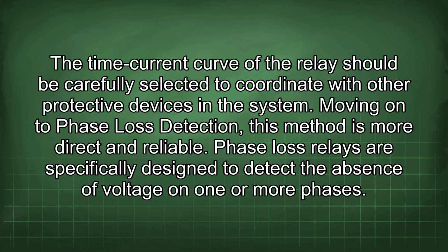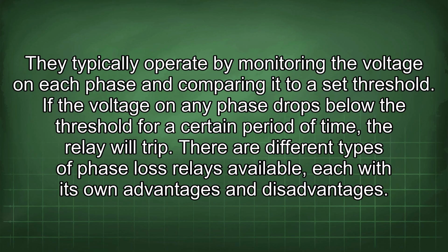Moving on to phase loss detection, this method is more direct and reliable. Phase loss relays are specifically designed to detect the absence of voltage on one or more phases. They typically operate by monitoring the voltage on each phase and comparing it to a set threshold. If the voltage on any phase drops below the threshold for a certain period of time, the relay will trip.